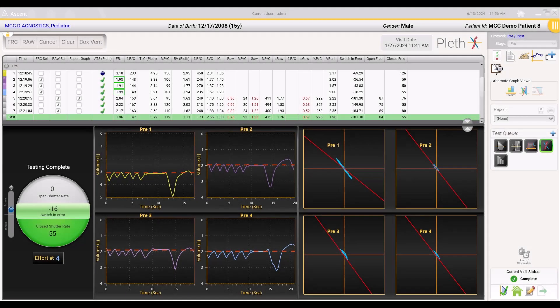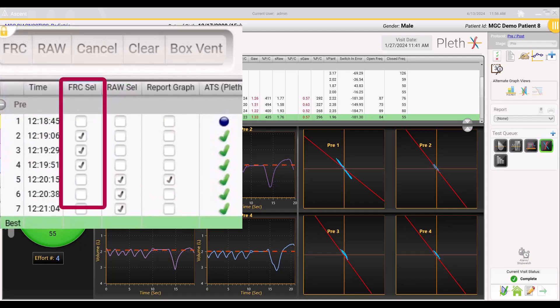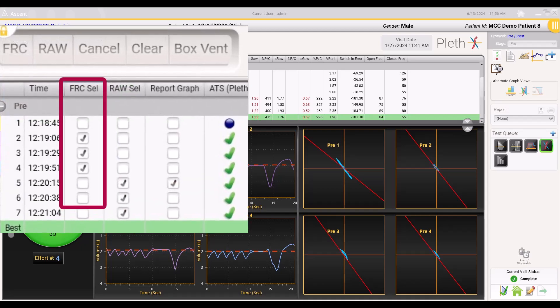Look at each tracing to see if the line of best fit is appropriate. Once all adjustments have been made, you can now check which efforts you want to average for the final report. For airway resistance testing, the graph will have two tracings overlapping each other. The blue tracing is the closed shutter breathing, which measures lung volumes as previously mentioned. The red tracing is the open shutter panting, which measures airway resistance.